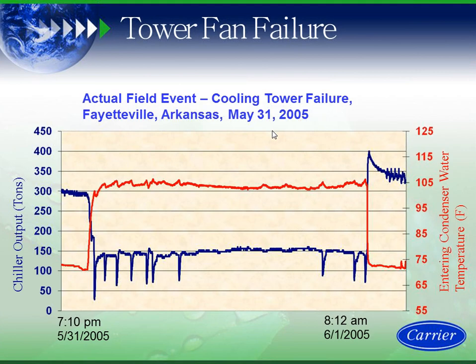One of the key things, and we're going to go into the performance here, is the real piece that makes people's eyes light up when we talk about this machine. We had a chiller that was one of the first beta site chillers, after it had been operating for a year in Fayetteville, Arkansas. This machine was running at around 300 tons when it experienced a tower fan failure. Carrier heard back from the operator that the chiller operated through a tower fan failure. This was pretty significant.